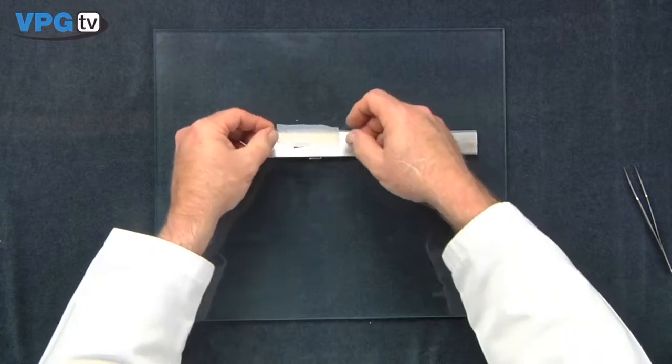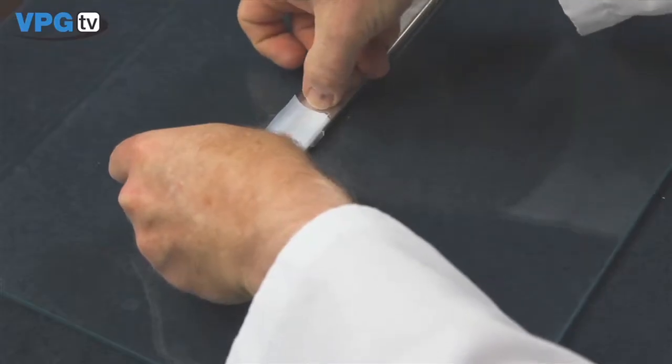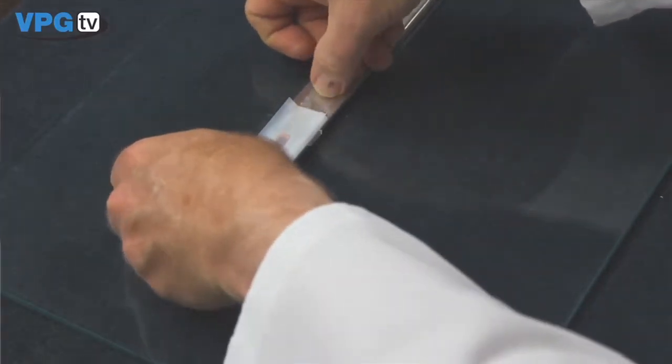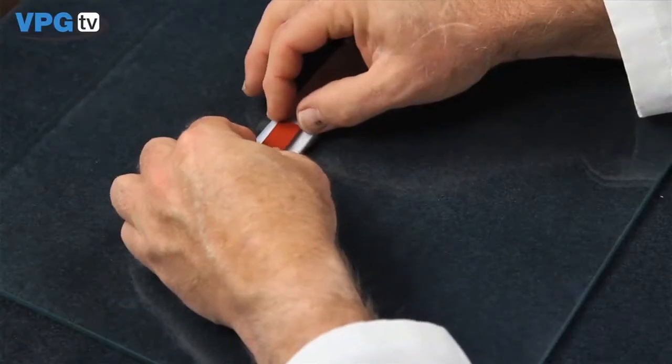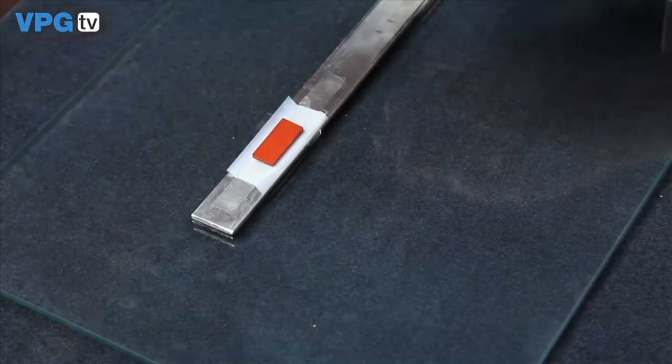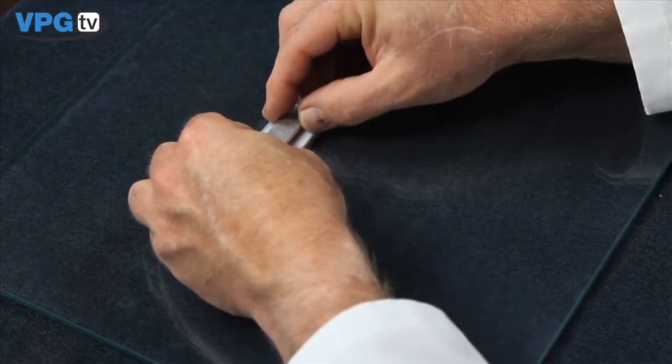Step four will cover clamping and M-Bond 610 cure requirements. Secure a short length of Teflon film over the gauge with two small pieces of Mylar tape. Place a silicon rubber pad on the Teflon directly over the gauge. To distribute the clamping force evenly, center a metal backup plate over the pad.